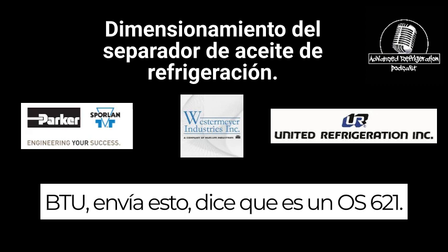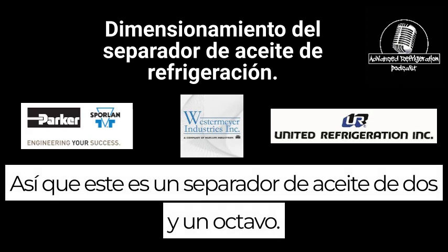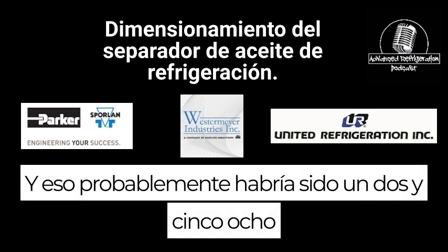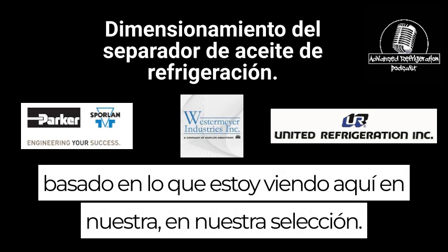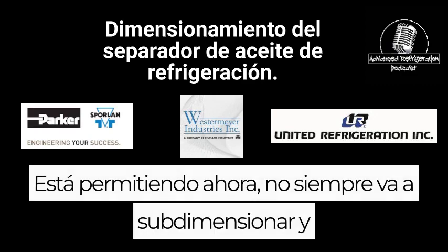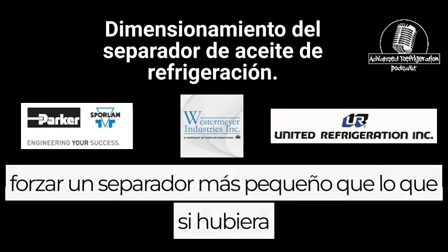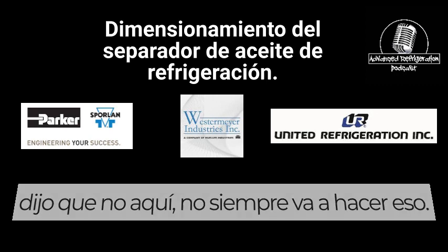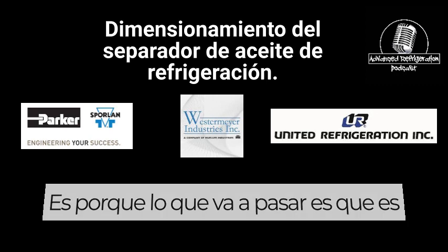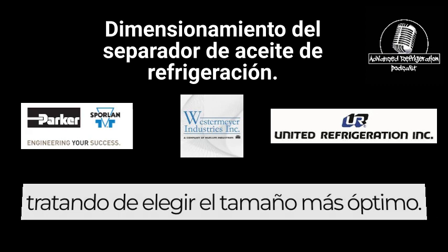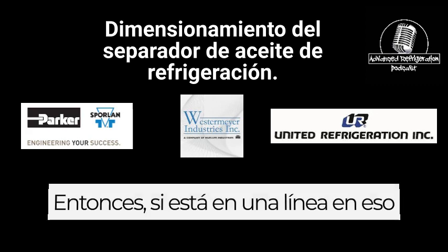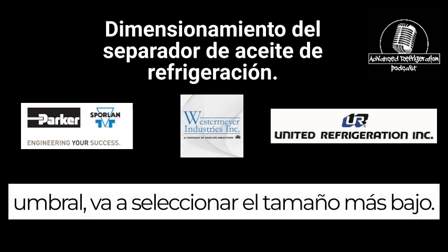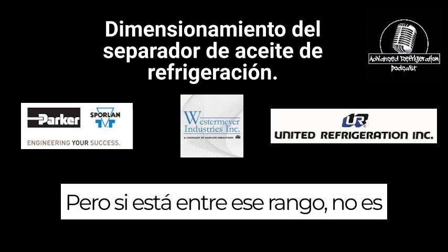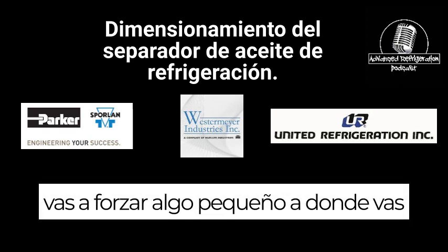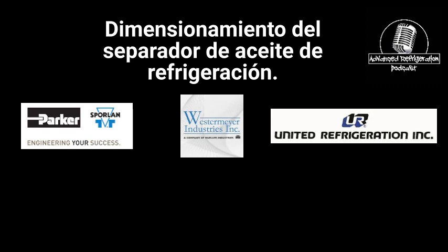We submit this. This says it's an OS6-21, so this is a 2 1/8 oil separator, and that likely would have been a 2 5/8 based on what I'm seeing here on our selection. So this is what this is doing. It's allowing it. Now it's not always going to undersize and force a separator smaller than what you would have gotten if you had said no here. It's because it's trying to pick the most optimal size. So if it's on a line on that threshold, it's going to select the size lower. But if it's in between that range, it's not going to force something small to where you're going to have a massive pressure drop calculation.